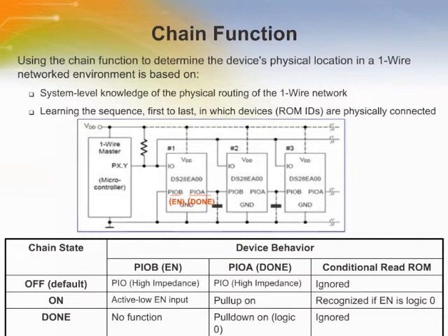The chain function is a feature that allows the one-wire master to discover the physical sequence of devices that are wired as a linear network. This is particularly convenient for devices that are installed at equal spacing along a long cable, for example, to measure temperatures at different locations inside a storage tower or tank. Without the chain function, the master needs a lookup table to correlate registration numbers to the physical location.